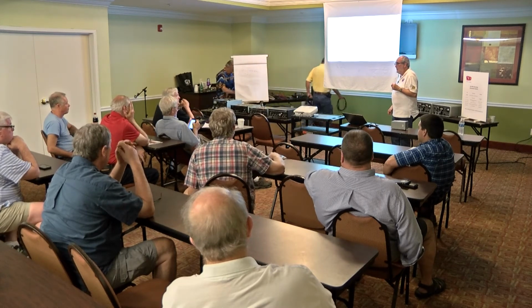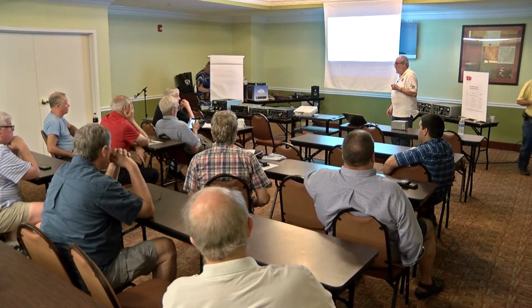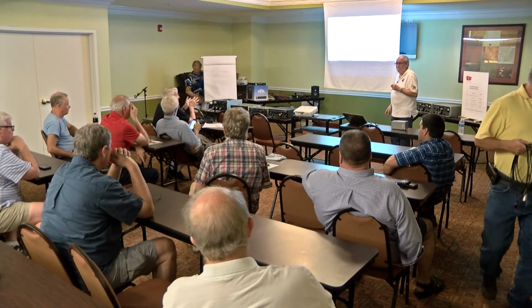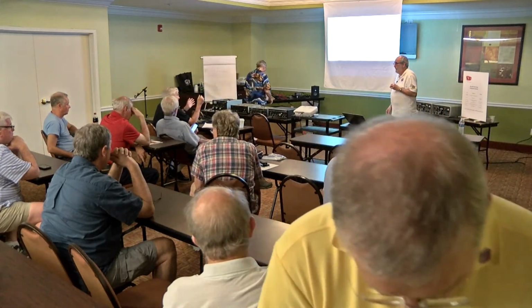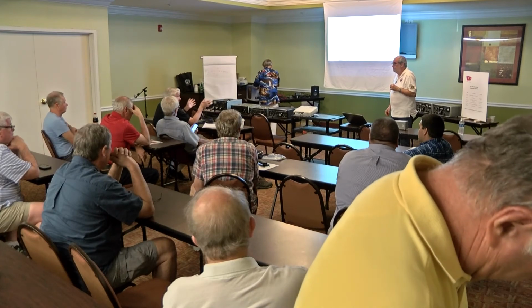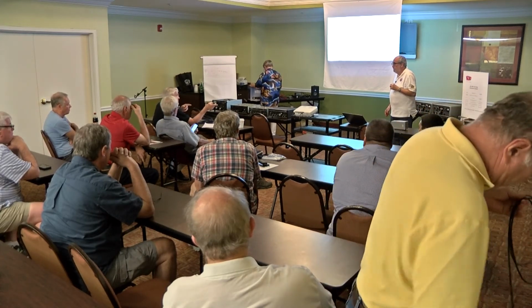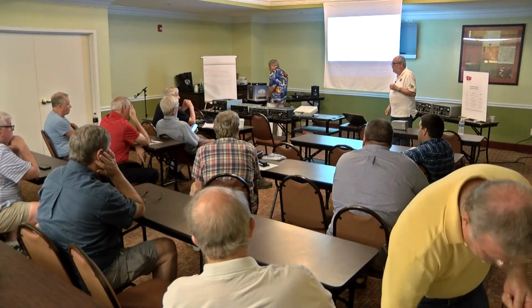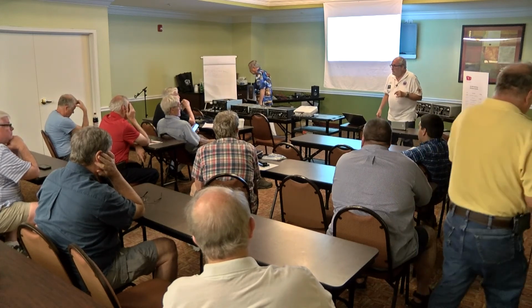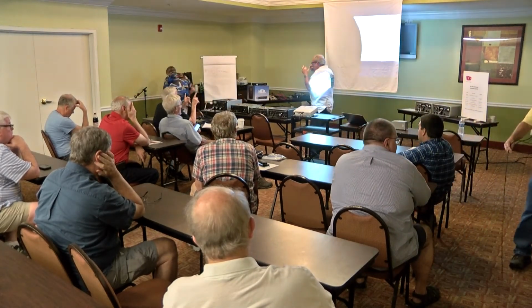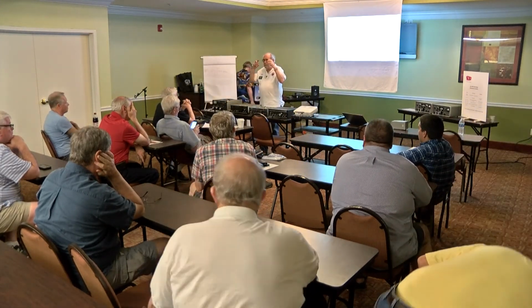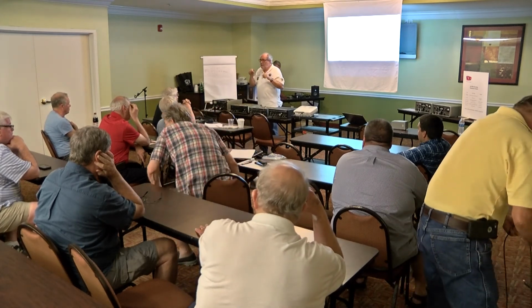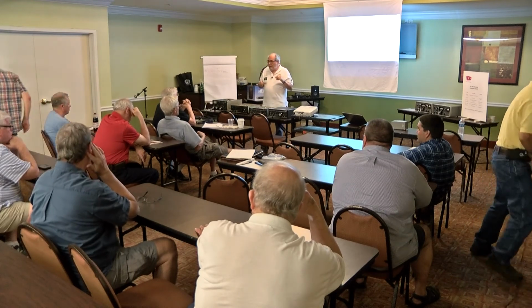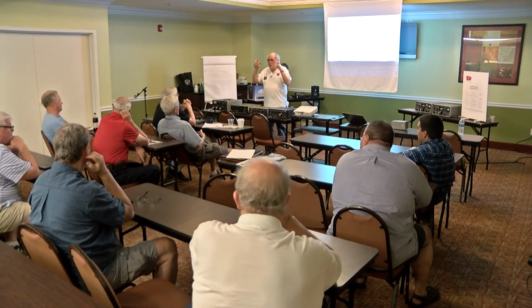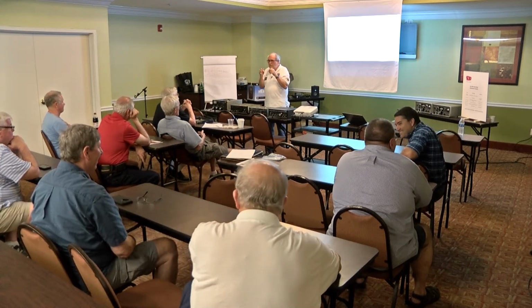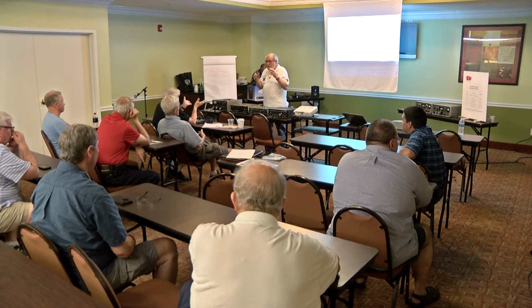Brother Dave, I have two questions. We started off this discussion talking about variable input AC voltage and how it affected our lower secondary voltage. If the voltage goes up on this, whether it's buck or boost, it's also going to change our secondary. So we're not doing any necessary stabilization. What we need to think about is that the change of the primary voltage over time is going to be tiny. In the case of John's shopping center load, his solution is to move, because there's no way a passive device like a transformer is going to compensate automatically for that.